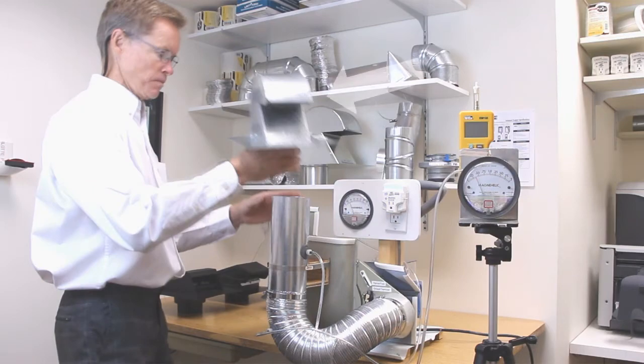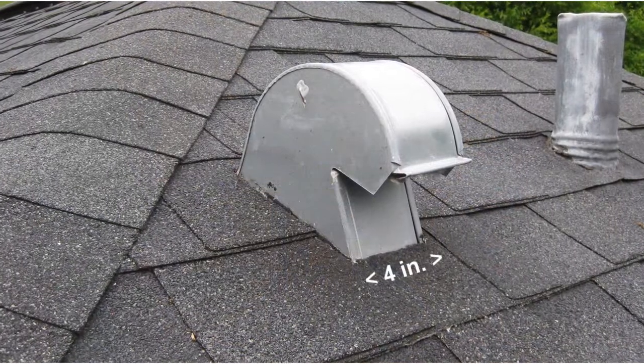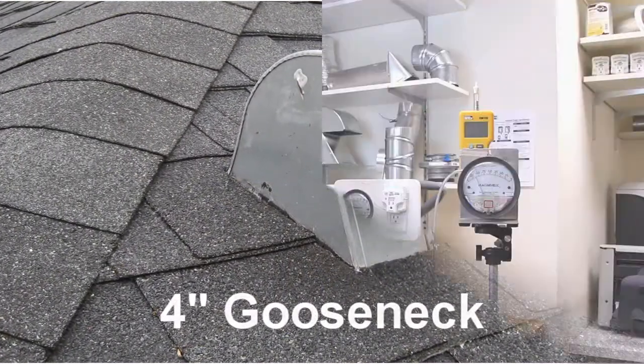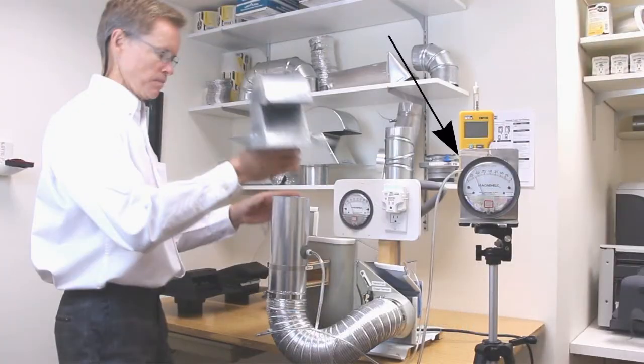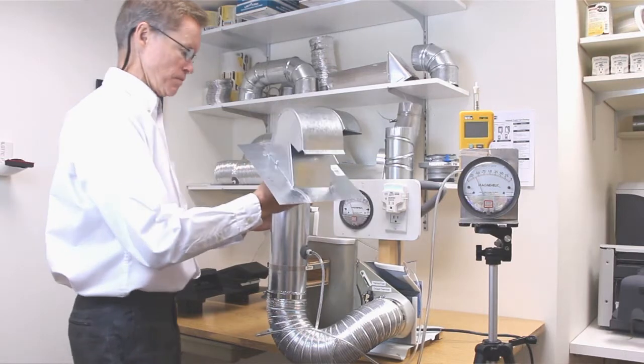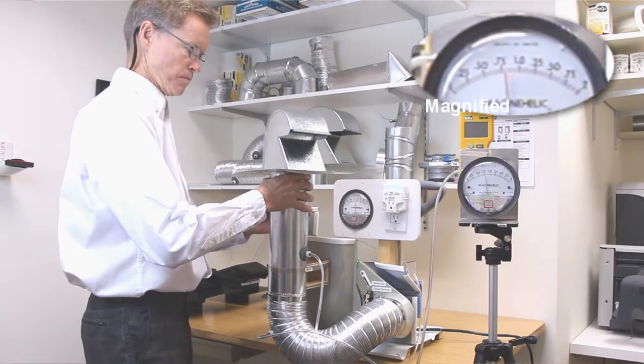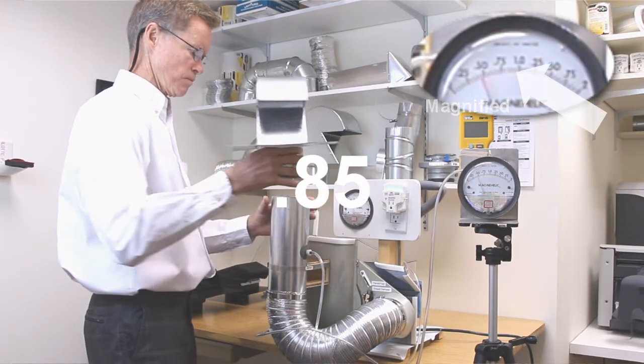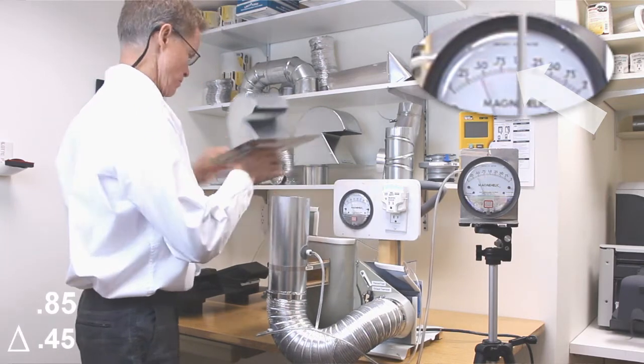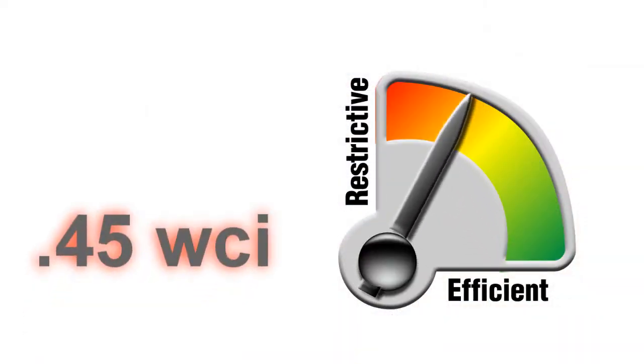This is possibly one of the most common roof vents for the dryer. It measures four inches across and is referred to as a four-inch gooseneck. Starting with a reasonably typical residential pressure of 0.40 water column inch, this vent increases the inline pressure to 0.85 water column inch. That's an increase of 0.45 inches of water column, and in our industry, that is considered excessive.